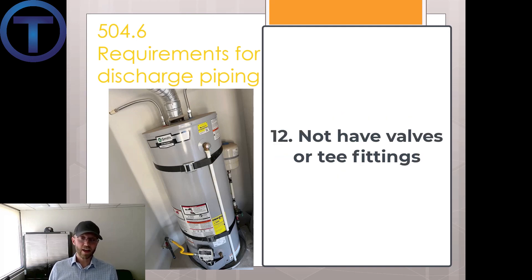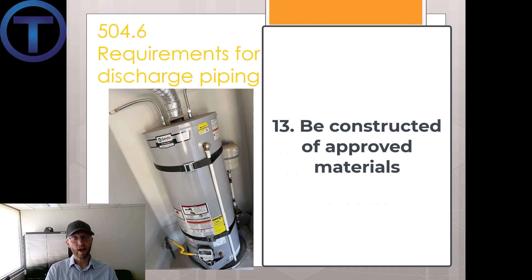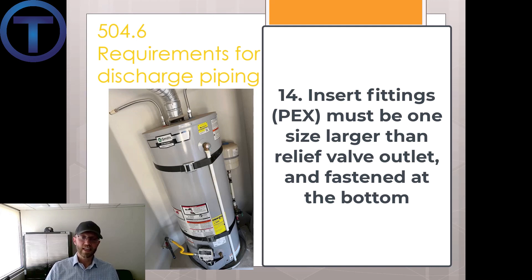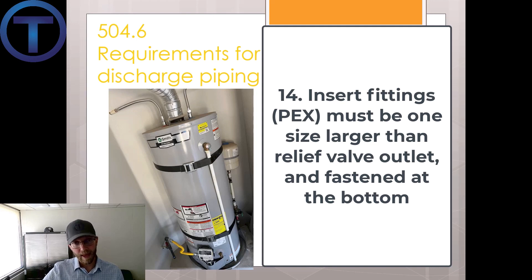Number twelve: it shall not have valves or T's. Number thirteen: shall be constructed of those specific materials listed — you can't just use whatever you want. Number fourteen: the pipe has to be one nominal size larger than the size of the relief valve outlet where the relief valve discharge piping is installed with insert fittings. In other words, if you're using PEX, a barbed PEX fitting shrinks down the inside diameter, so you need to use a larger pipe.